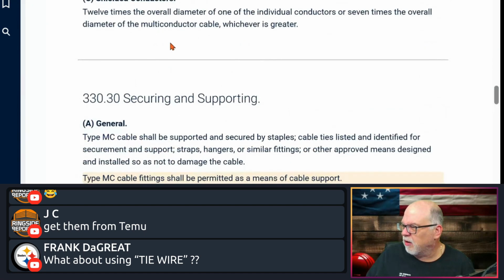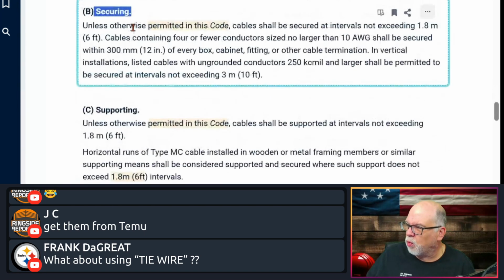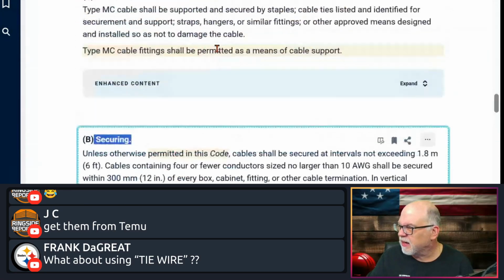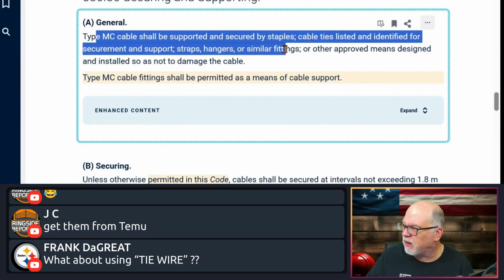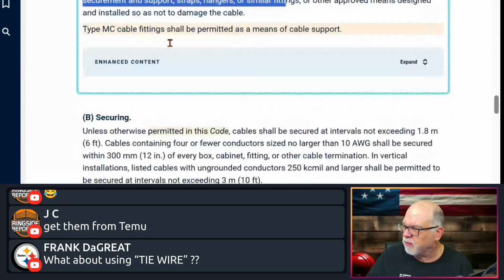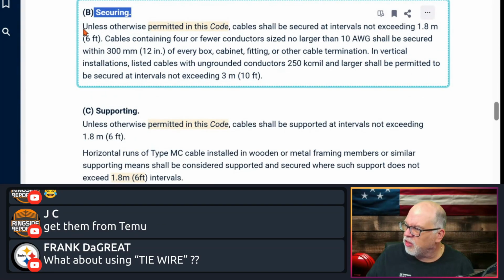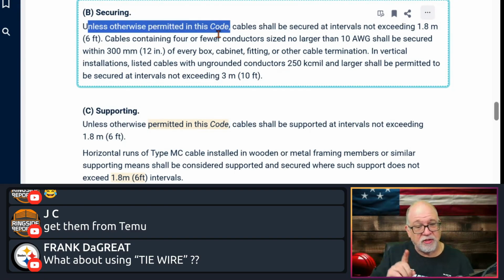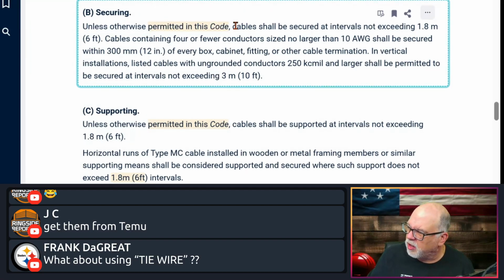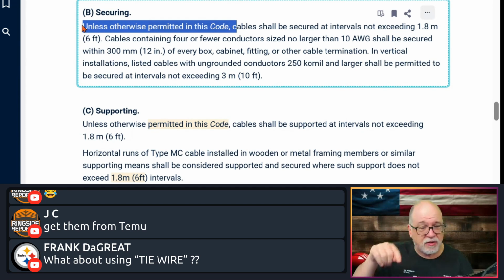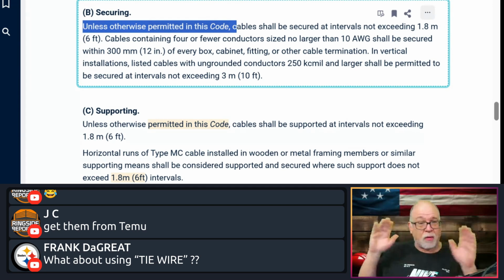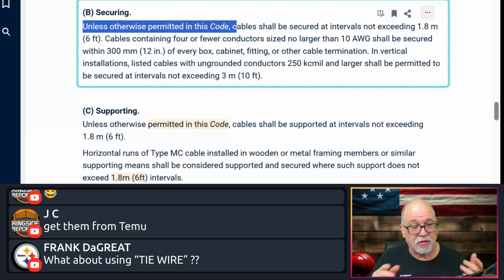All right, so anyway, where are we at? Okay, so let's get down in securing. All right, so what are the rules with securing? Because for the supporting, we says right here, in general, we have to support and secure it. We can use these types of methods, okay? Even Frank's tie wire, if the AHJ is okay with it. Now, securing, unless otherwise permitted in the code. That's an important statement because you're going to have permission for unsupported cables here in a second. But it says, unless otherwise permitted in the code, that means if somewhere else in the code deviates from this, it's okay because somewhere else in the code says it's okay. Okay. Remember, chapters 1, 2, and 3, and 4 are general, right?